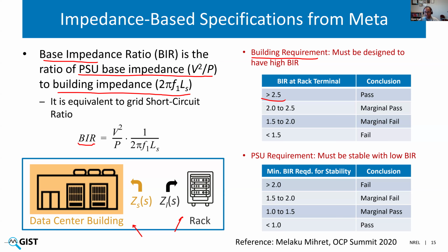If BIR is more than 2.5, it's considered a pass. And as you go lower, you basically make the grid weak, in a sense, for the IT racks. There is a similar requirement for PSUs, where we want the PSU to remain stable even for a BIR which is less than 1. So we are really talking about very weak grid conditions compared to the frame of reference of the SCR that we use.